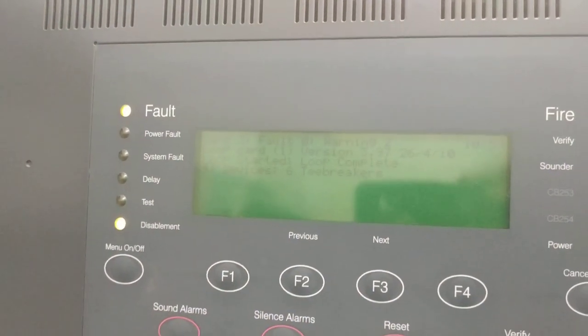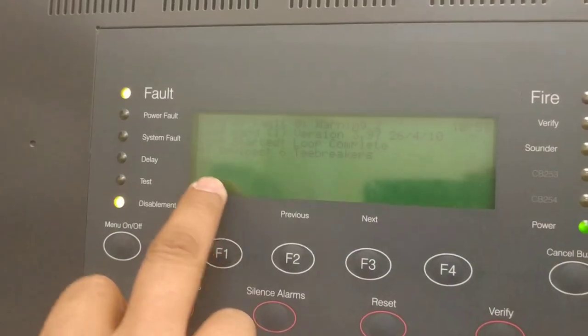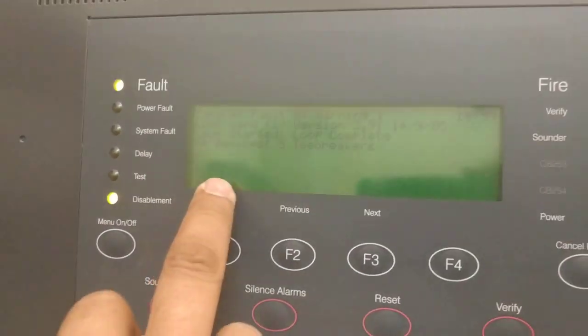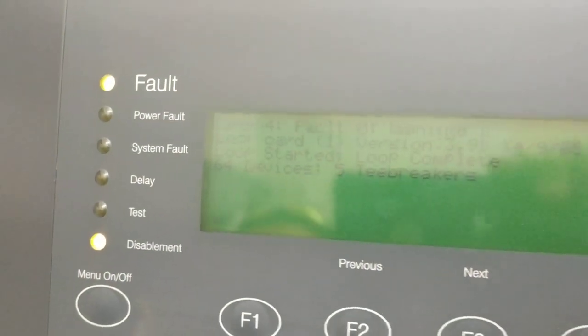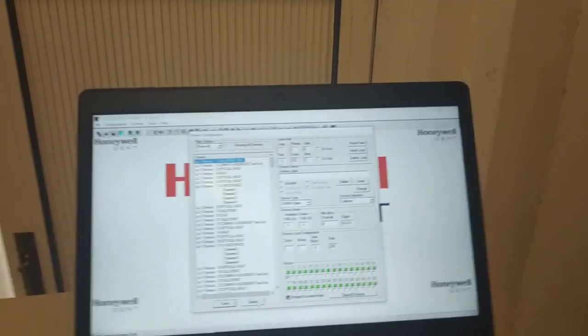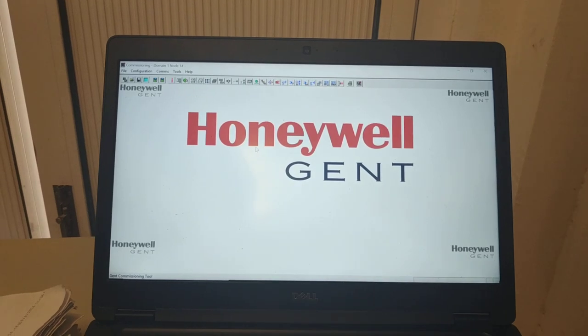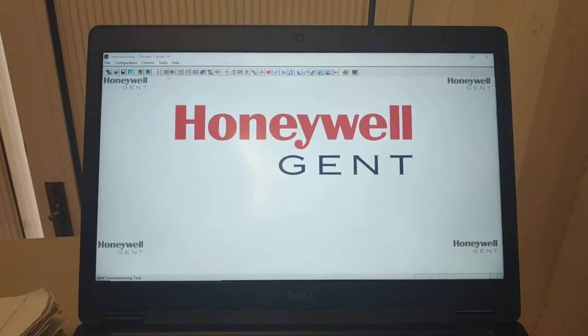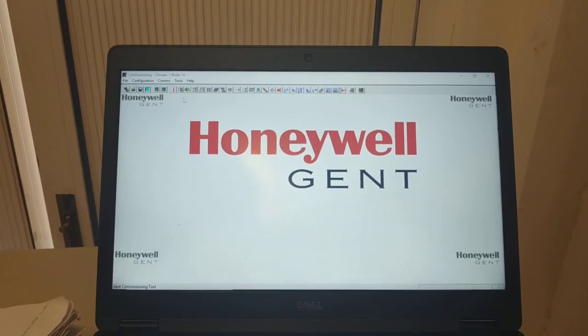Loop 2 is loop split. Loop 1 has 69 devices only — loop complete. Loop 3 has 47 devices — loop complete. Loop 4 has 64 devices — loop complete. Now I need to record this. I'm scared the existing program, so first thing I will just cancel this and check what is the scenario of the program before device configuration.